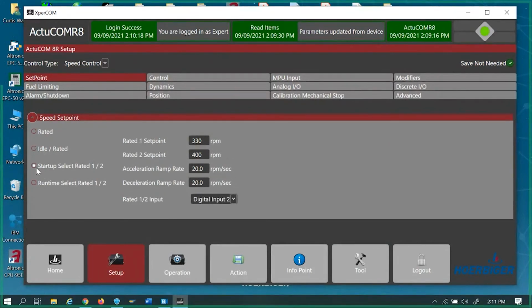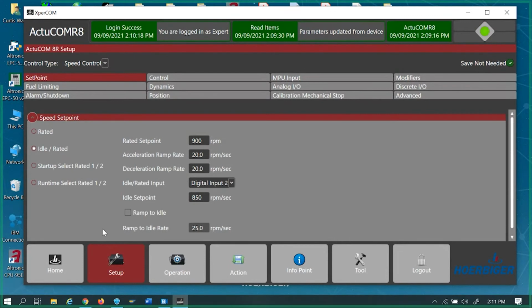We can do some different startups, some different ramps, if we wanted to. Say you wanted to do a different startup with maybe a different type of fuel. You could ground out one of our digital inputs that says go to my number 1 selected rated or go to number 2 selected rated. I have never used this yet, but then again, I mainly deal with gas compression or pump type engines. So we have a rated set point, and acceleration ramps, which is how fast it'll go up to this set point. Deceleration is how fast you drop. Pretty simple. Idle rated shows you what input you'd have to touch or ground or add 24 volt to.